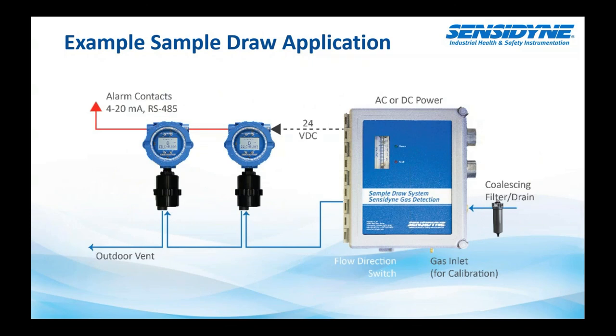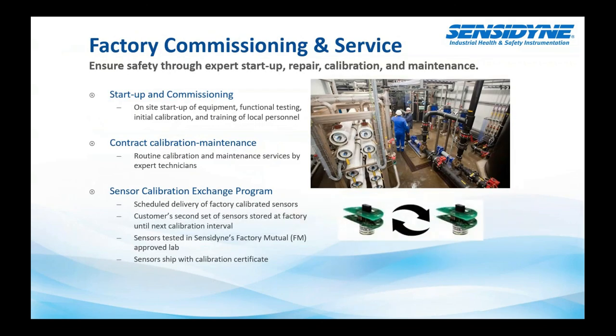Kind of already went over this, but same kind of thing. You can pass this across multiple sensors, draw from a single point, condition or filter your sample so that you're prolonging the life of your sensors. So as I said, all the sensors are portable. This gives us the ability to do calibrations either in a controlled environment like the maintenance shop. You can have a spare transmitter there, do your calibrations remotely, and then go back and exchange the sensor in the field. That way you're not doing it out in the field in the heat, the moisture, and the different things that affect the calibration, as well as the employee's safety and comfort.